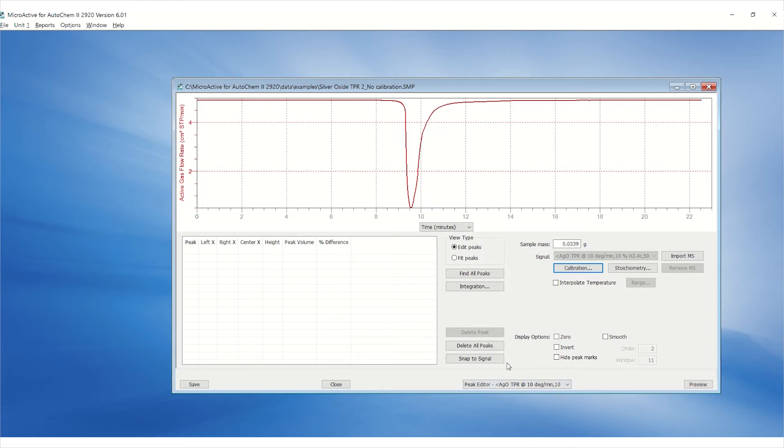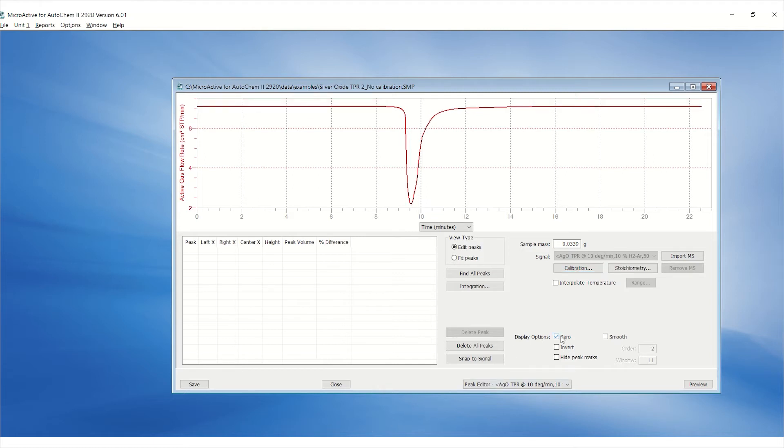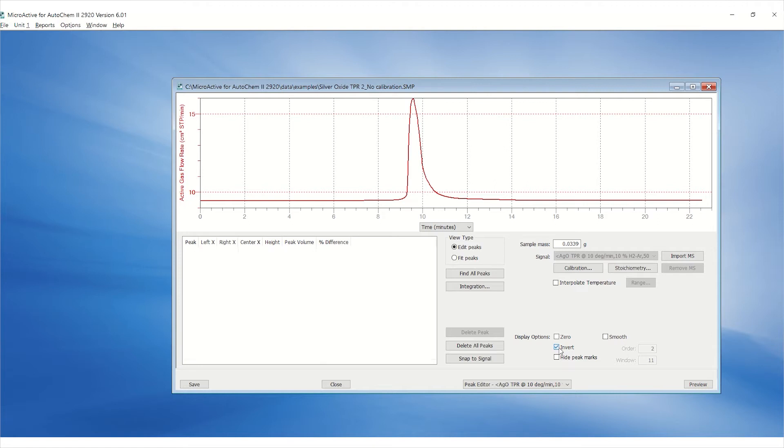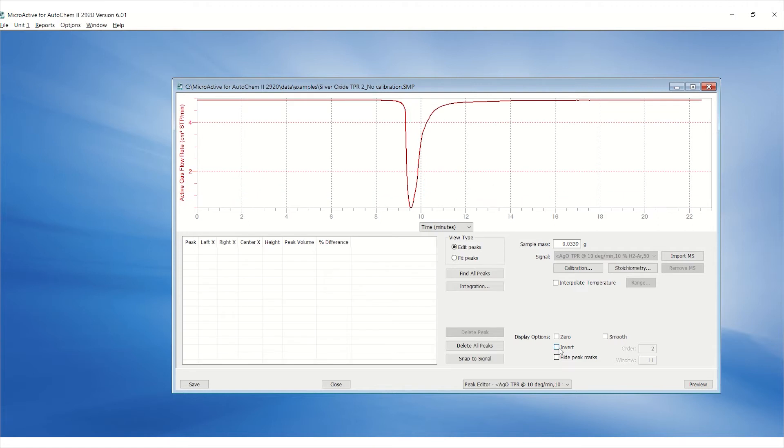Select the display options appropriately. Make sure the zero and invert TCD signal match the calibration file in use.